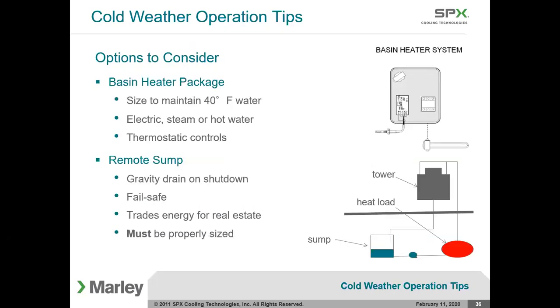Okay, some options to consider. We can get a basin heater package. So that basin, if it's cold enough weather, can actually freeze up. So it could be strip heat. It could actually be from some other heat source if you wanted to. But usually sized to maintain 40 degrees in the basin. Like I said, it could be electric, steam, or hot water. And we have thermostatic controls so that it doesn't just run all the time. It only runs when it's trying to get below 40.